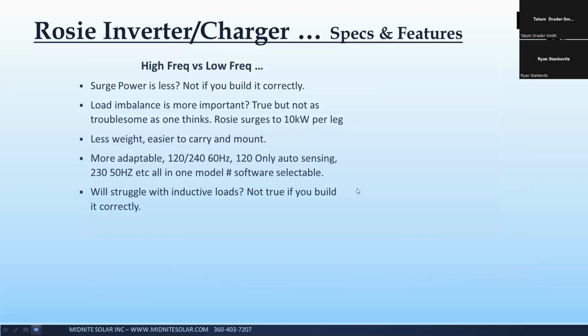And then some of the other ones you'll hear is that surge power is less on high frequency. And this just isn't true if you build it correctly. One of the things where this comes from is that you can go to any little hardware store, Walmart, Amazon, any of your auto parts stores, and you can buy these very inexpensive modified sine wave, generally speaking, high frequency inverters. And those inverters will not surge. That is true. But if you build it correctly, you use the right parts.